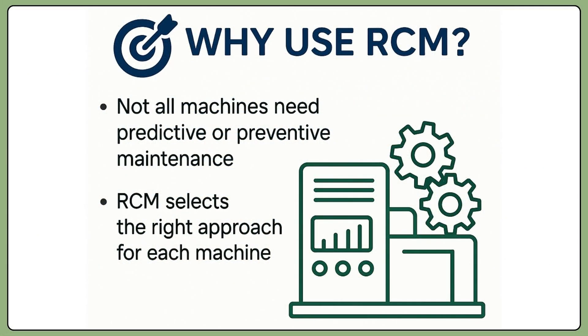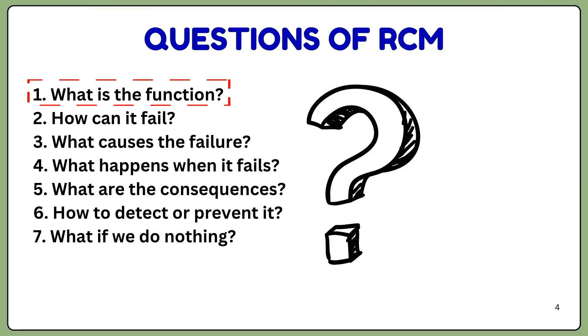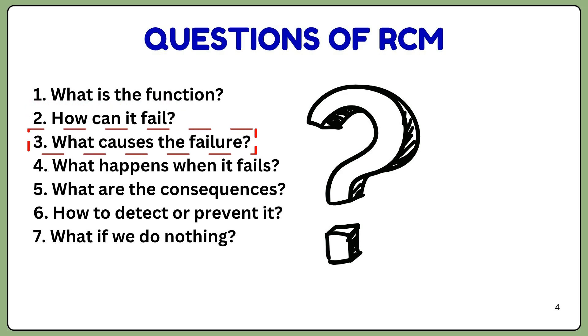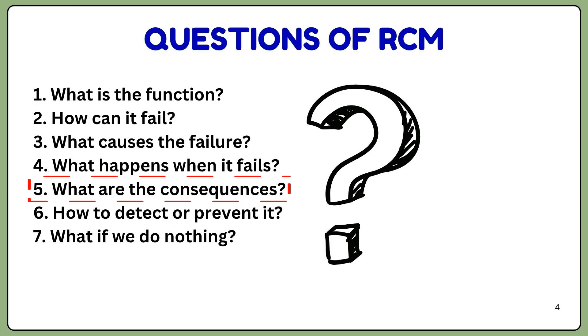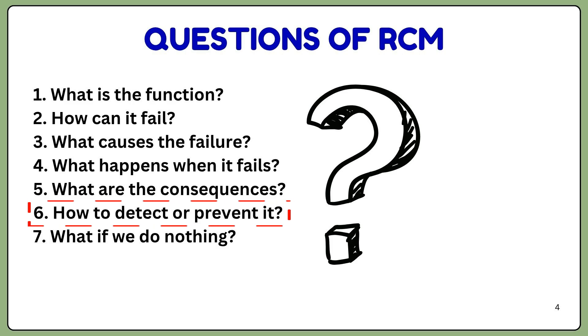When applying the RCM process to any critical asset, you should ask yourself seven questions. First: what is the function of this equipment? Second: how can it fail? Third: what are the causes for each type of failure — you write down all failure types and map each to its causes. Fourth: what happens when it fails and what is the impact? Fifth: how does it affect operations or safety? Sixth: what can we do to detect it or prevent it? And seventh: what happens if we do nothing?